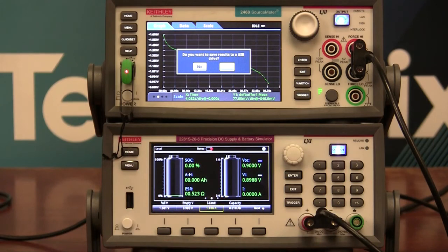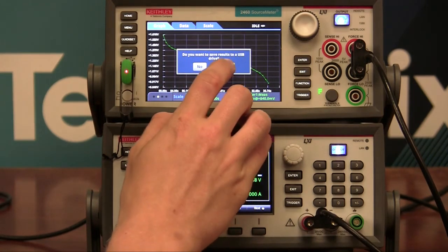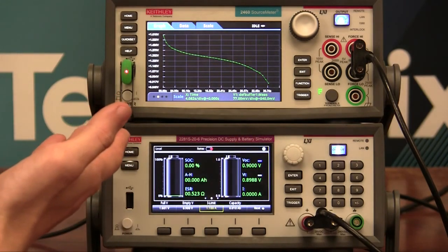Now that was very fast. In reality, a battery discharge would take days or sometimes weeks. So when it's done, it says, do you want to save the results to a USB drive? In this case, yes. And now it just saved that model onto the USB drive of this battery discharge.